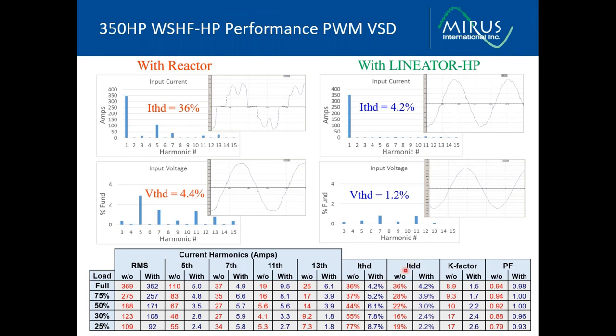IEEE 519 is one of the standards that introduces total demand distortion. Total demand distortion reflects the relationship between total harmonic distortion and the actual loading on the system. So at full load, THD and TDD are the same. We can see at 50% load, the TDD is 50% of the THD, because to calculate TDD, we take the THD and multiply it by the actual current divided by the full load current. And that will determine our TDD.